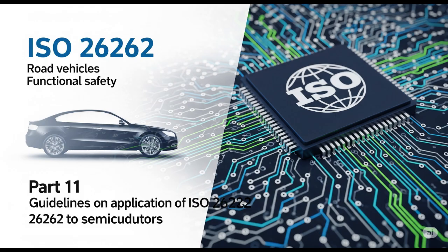Clever. For MEMS pressure sensors, redundant diaphragms are sometimes used. This involves having a second, non-moving reference diaphragm built right next to the primary sensing diaphragm. Comparing the signals from both allows the system to detect drift or failure in the primary sensor. There are also various transducer-specific self-tests designed to verify the integrity of the entire signal path, from the physical sensing element right through to the electrical output.